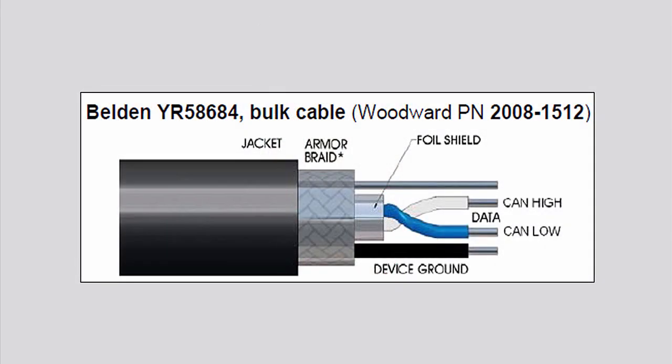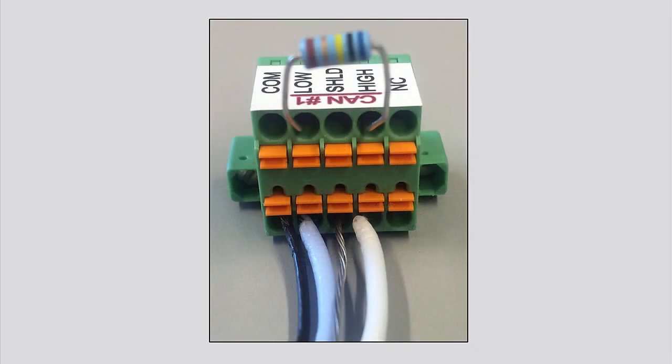To wire to the controller's CAN connections, Woodward recommends the Belden YR58684 communications CAN cable. This is a smaller and flexible 22-gauge low-capacitance cable suitable for tight routing in industrial environments. For robust communications performance, the CAN cabling needs to minimize the exposed non-shielded cable section that occurs at terminal blocks. The exposed length of CAN wiring must be limited to less than 3.8 cm or 1.5 inches from the end of the shield to the terminal block.